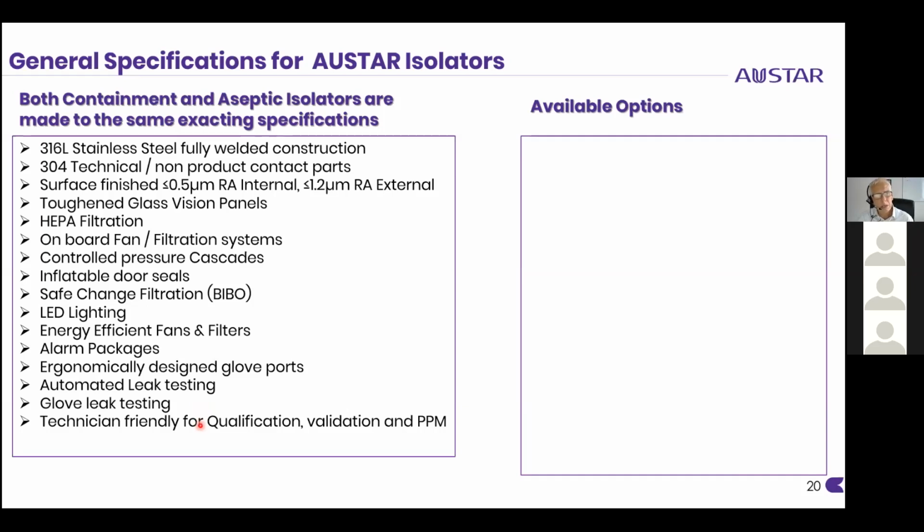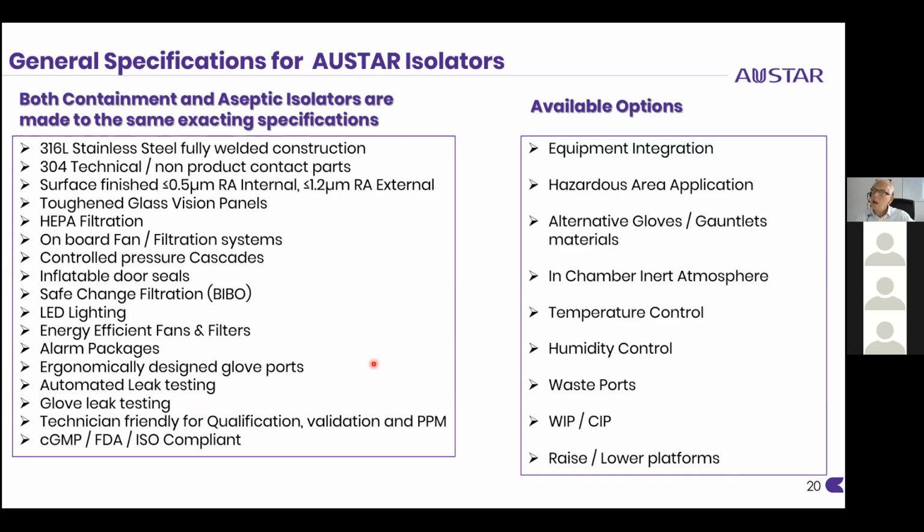And we design our isolators to be technician friendly for qualification, for validation, also planned preventative maintenance. There's simple things like calibrating pressure transmitters. We try and ensure it's easy for everybody to use our isolators. And obviously we have to comply with CGMP, FDA and ISO and other standards. And there's a lot of available options, many options for many different processes.